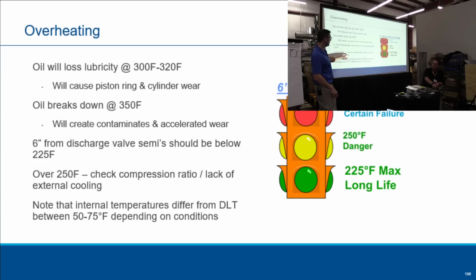Over 250 degrees Fahrenheit, check compression ratio. And lack of external cooling, like Don said, check this compression ratio. If you put your temperature probe on and it's 250, is that okay? Note, I just said this, internal temperature is 50 to 75 degrees hotter.